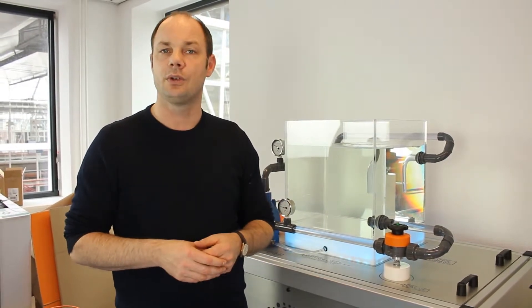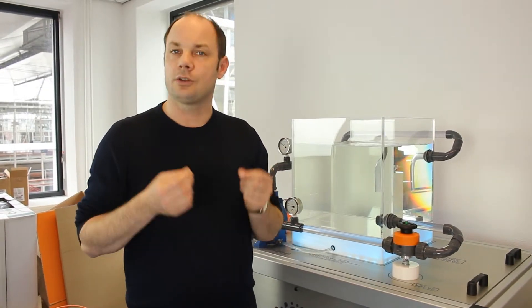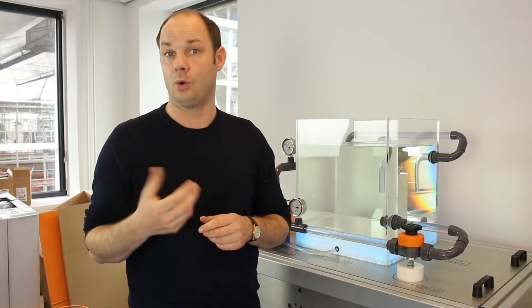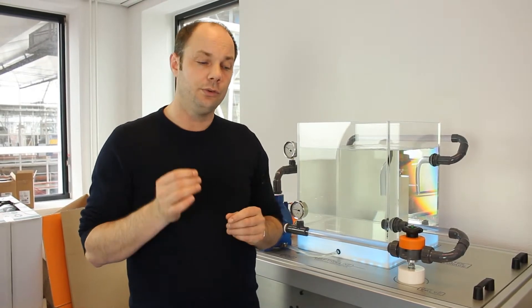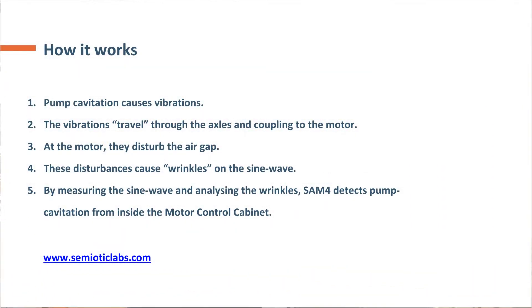The process is fairly straightforward. When cavitation is introduced, what starts to happen in the pump is it will start to vibrate in a markedly different manner than when it's operating in normal mode on the curve. In traditional solutions you pick up that vibration by installing a vibration sensor. However, that same vibration travels from the axle of the pump through the coupling to the axle of the motor. At the motor it will disturb the air gap that sits between the stator and the rotor. When you disturb that air gap it will introduce wrinkles on your sine wave. By measuring those wrinkles and by analyzing them, we can effectively detect cavitation using electrical waveform analysis.